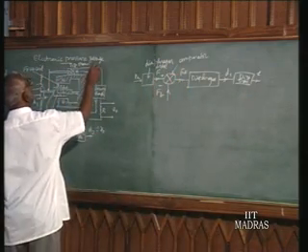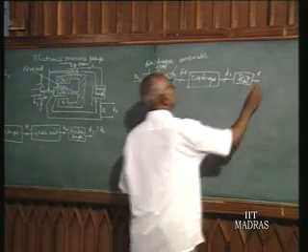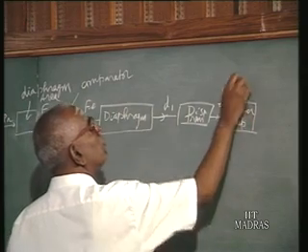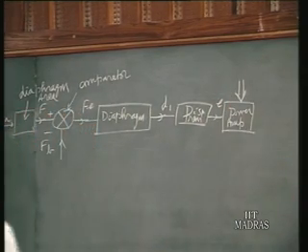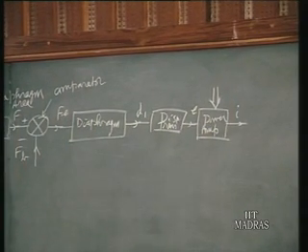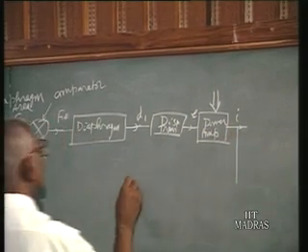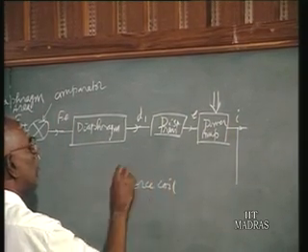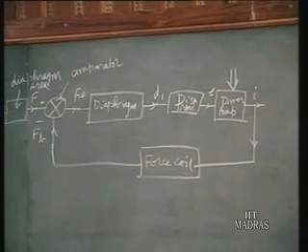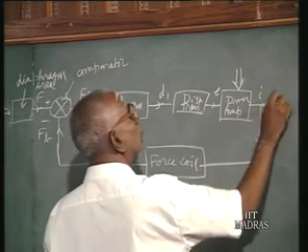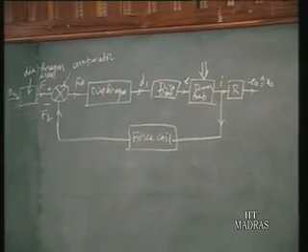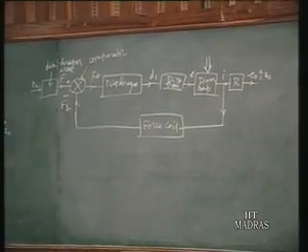The converted voltage E goes to the power amplifier, where energy input is there. Then we have a current flow I as the output from the power amplifier, and this current is taken to the force coil. This force coil gives rise to FB. The current also flows through a resistor R and gives rise to EO, which is our output signal. So this is the signal flow diagram for this electronic pressure gauge.